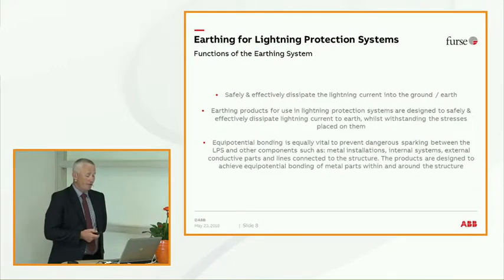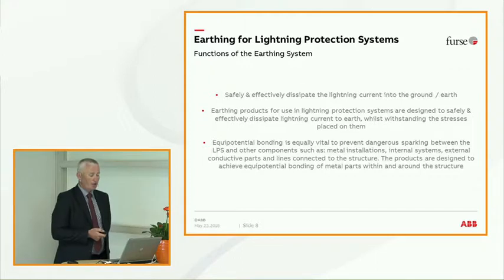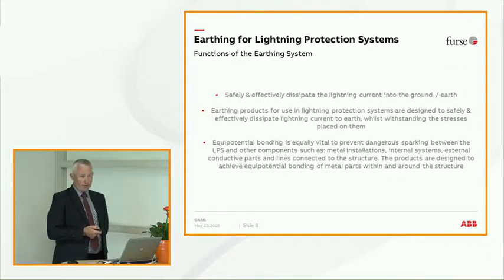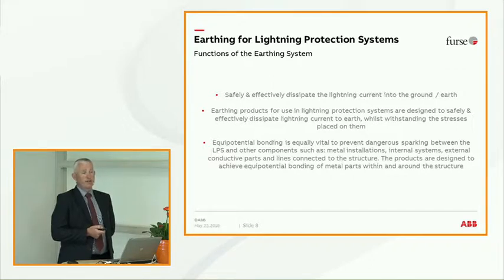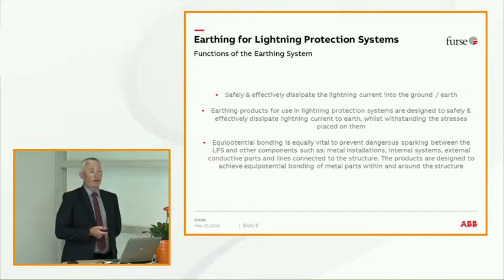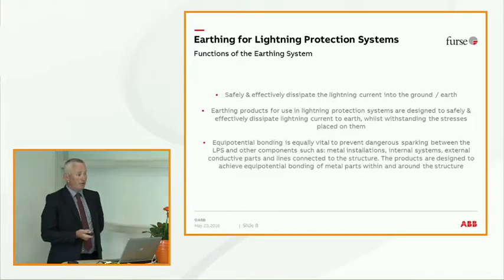When we're looking at lightning protection, as I said, it's to safely take the current to Earth. The materials used are designed to effectively dissipate that lightning strike and withstand the stresses put on them by the strike itself. Equipotential bonding is a critical part of lightning protection. This means that we don't want any flashover currents, so if we're talking air conditioning units, ladders and aerials, there are several factors that need to be bonded in to make sure that the electric current goes the least path to Earth.